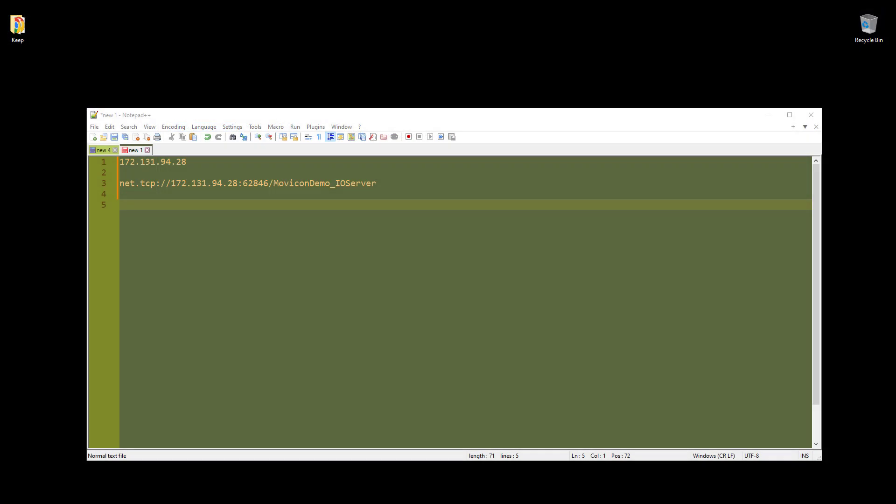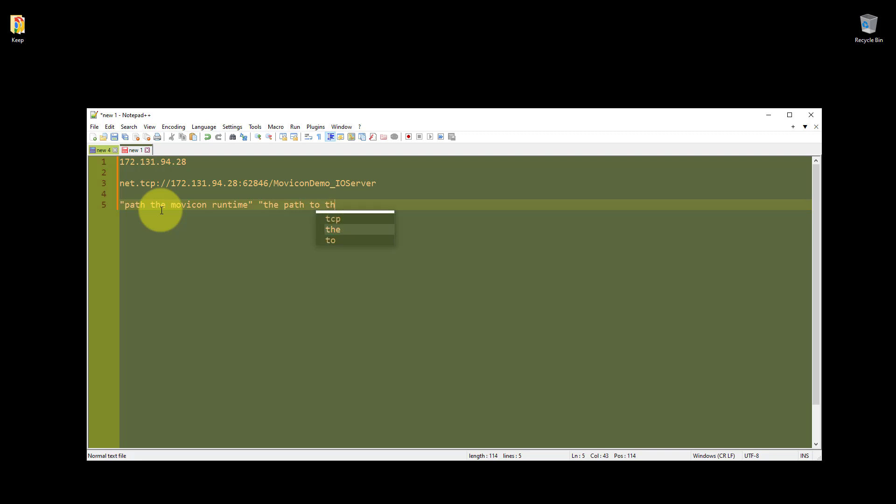So to create the shortcut for the client, I've opened up Notepad++ again. And what we basically need is the path to the Movicon Runtime, and we need that in speech marks. We then need the path to the project in speech marks. And then all we do is put these two switches at the end, Client and Start.